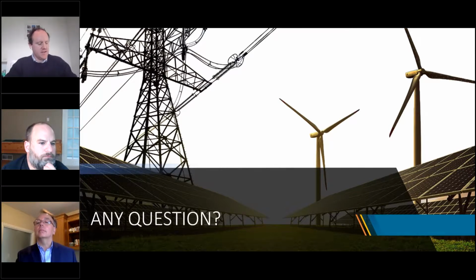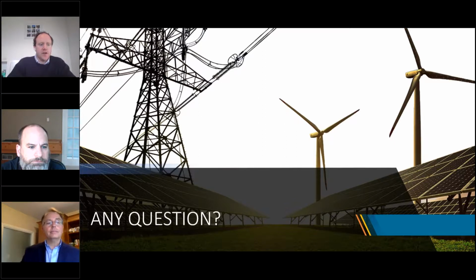Yeah, that's a good question, and you're right. If you're increasing the impedance of a circuit, then you're lowering the voltage across that line. But on the flip side, if you series compensate a line, you lower the reactance of the circuit, you're actually boosting the voltage in a particular area of the network. With SmartWires, we've had a number of applications where we're series compensating circuits to boost the voltage, not for thermal power flow control reasons, but for actual voltage control. And again, as Marc mentioned, these are voltage source converter technology, so they can be actively used to control voltage or power or current in real time. It would depend on the application, but I would first look at what impact you can have to lower thermal limits, and then check the voltage limits after that.